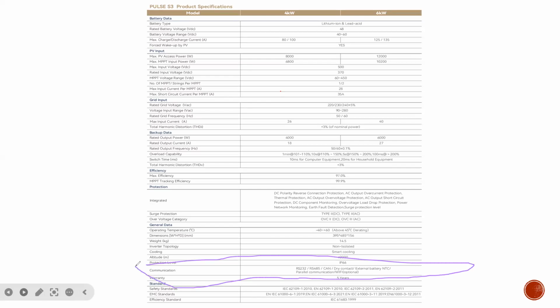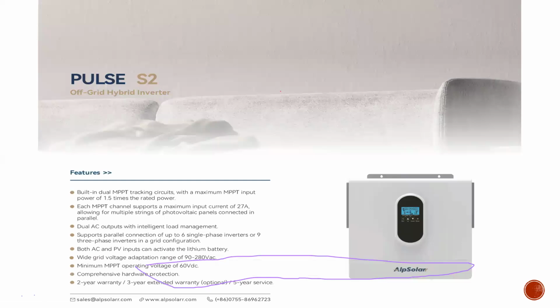So I'll move straight to our Pulse S2, which is our 11 kilowatt system. The first thing you're seeing there is that it has built-in dual MPPT, right? Our 6 kilowatt inverter has just a single MPPT, while our 11 kilowatt inverter, which is Pulse S2, has 2 MPPT, right? And it has a PV input power of 1.5 times its rated power. So this is an 11 kilowatt inverter, but it has a PV input power accommodation that is 1.5 times. So that means it has 16,500 PV accommodation.